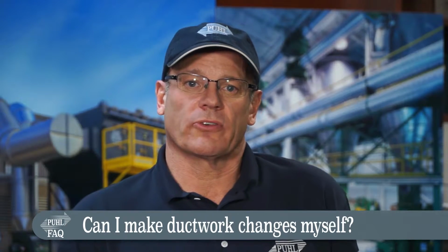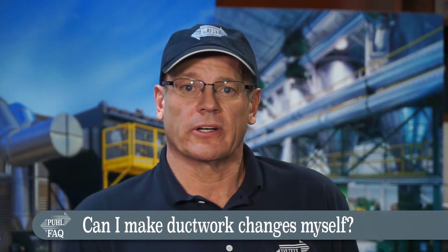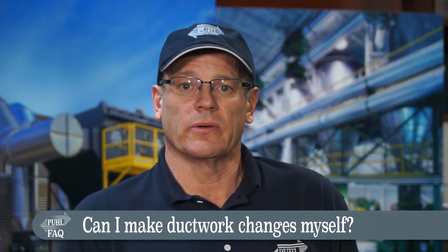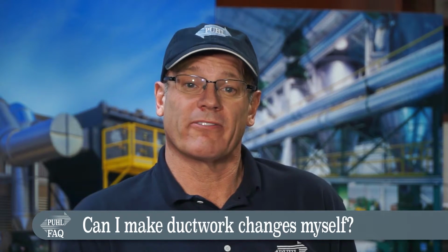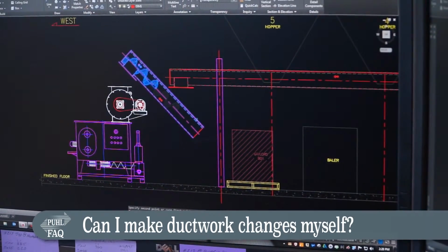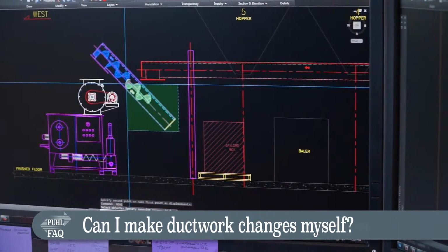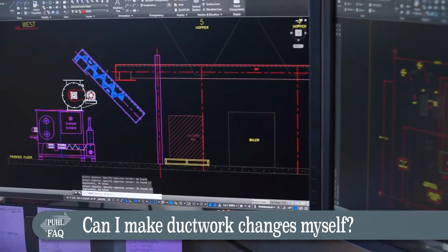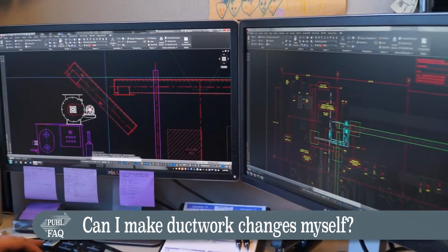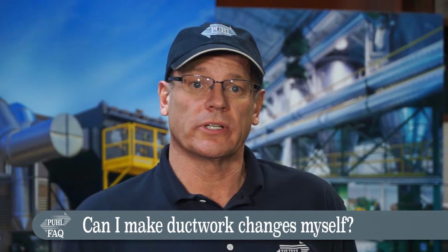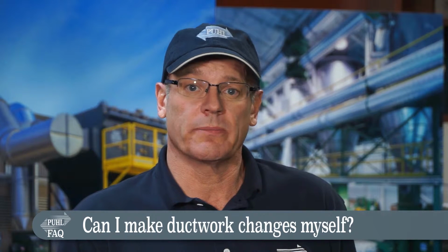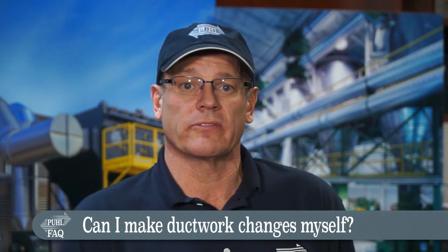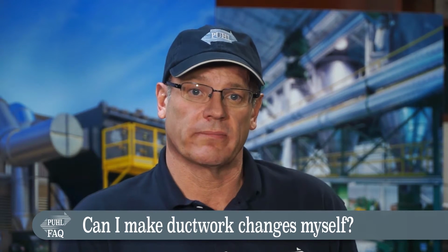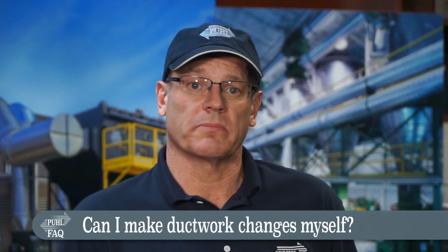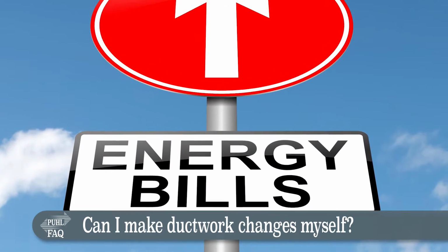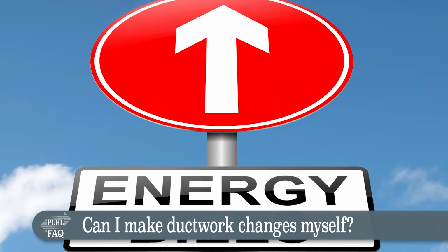Consider the implications for your power bill. In the average electric cost per kilowatt hour state in the USA, 1 horsepower costs about $500 per year. Missing the duct design can easily cause you to have to run a blower 10 or more horsepower above the optimal design. Inexperienced operators using do-it-yourself design for ductwork changes typically miss the optimum design by 10 to 50 horsepower on each system. Missing low means your system plugs up. Missing high means profits drain off in the form of a higher electric bill.